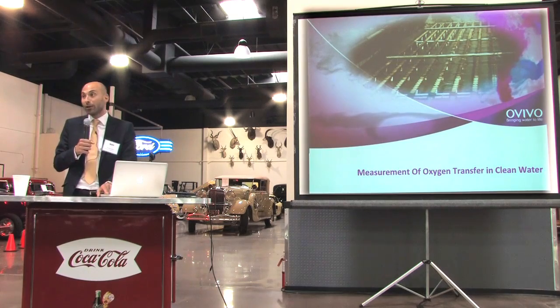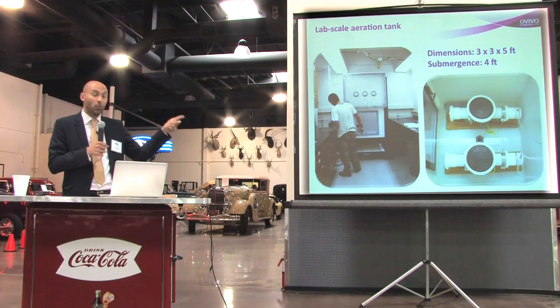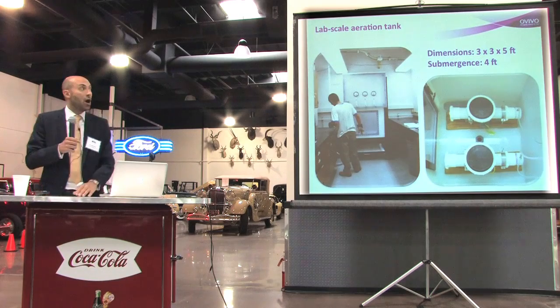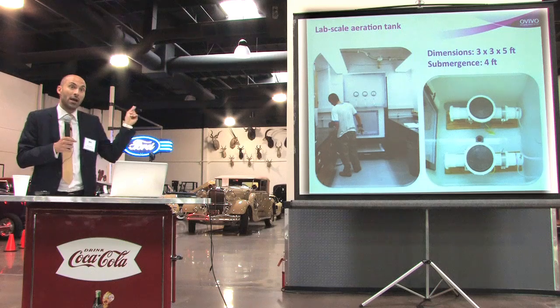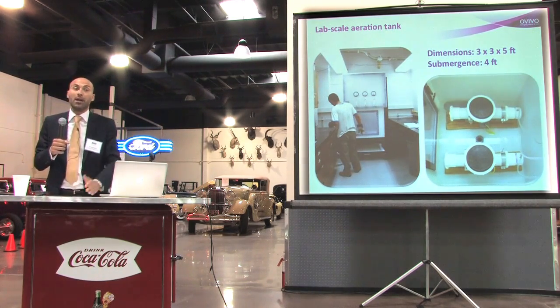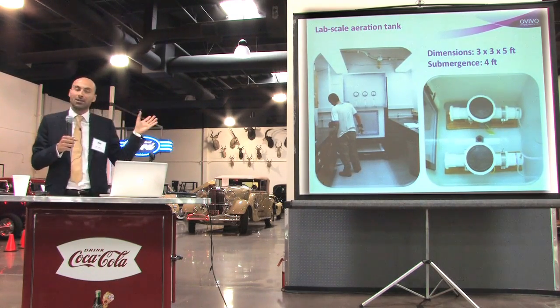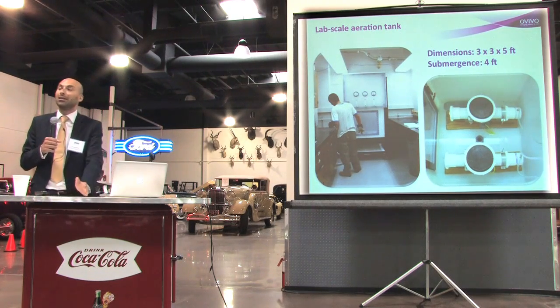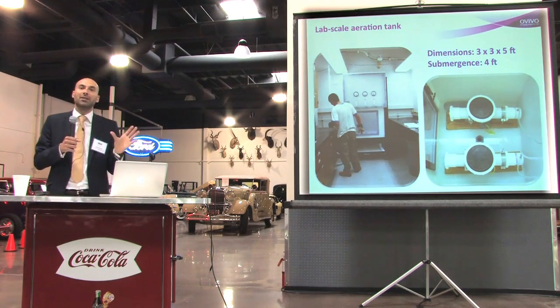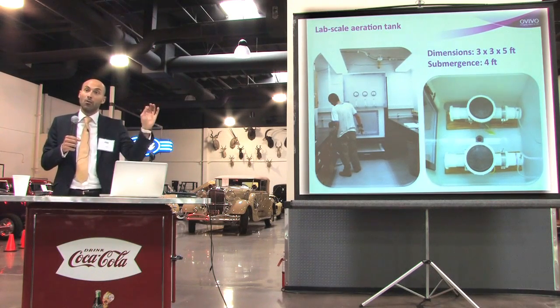I'll briefly show how a clean water test looks in a small lab tank — it's not the tank a manufacturer uses for certification, but here we can photograph bubble size distribution through a window. In the same tank we can test diffusers harvested from the field, and we have it continuously circulating mixed liquor at Urban Rancho Water District, so we can do a process test in the same geometry, letting the geometry effect cancel out to measure relative alpha and fouling factor.